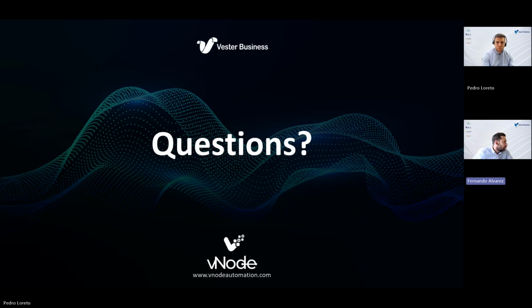Jayesh was asking how many vNode modules we will need for REST API at field level and client at SAP level, and whether any other module from vNode is to be used. Well, normally we need at least two modules. One for the data acquisition. Depending on where you need to read data from, OPC Classic, OPC UA, Modbus, you could use only one module or more than one, depending on your data sources. At least one module for data acquisition, and then another module for data delivery. With SAP, we use the REST API module. So at least you will need two modules.